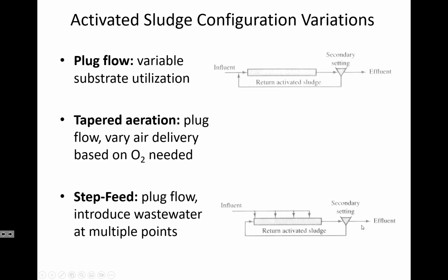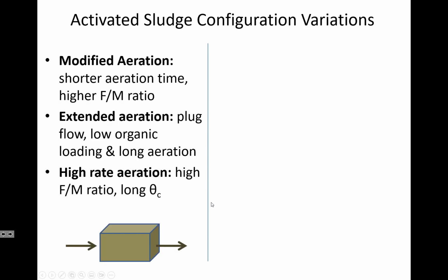In the case of step feed reaction, where water is coming in, this is plug flow, but step feed, the idea here is simply that by having the food decrease and then go back up again, decrease and then go back up again, you could nurture a different type of ecosystem than if you just had a single plug flow reaction. And you could step feed both the wastewater and the oxygen and have periods of anaerobic activity that are more advantageous for removing nutrients.